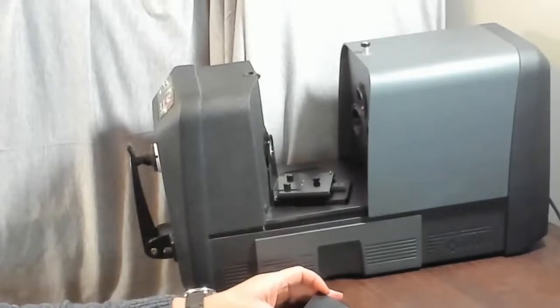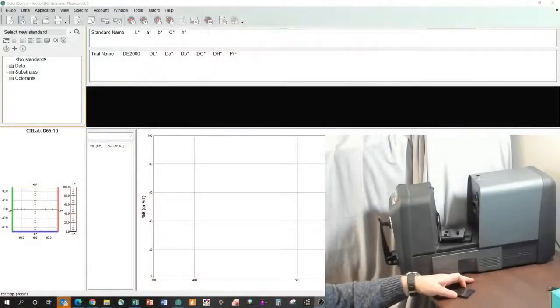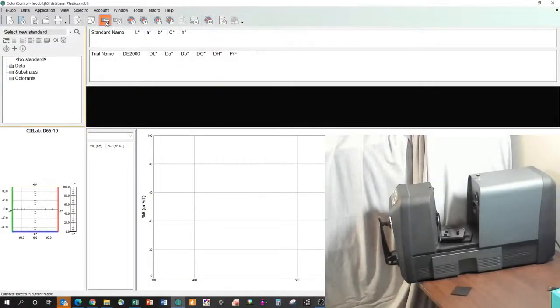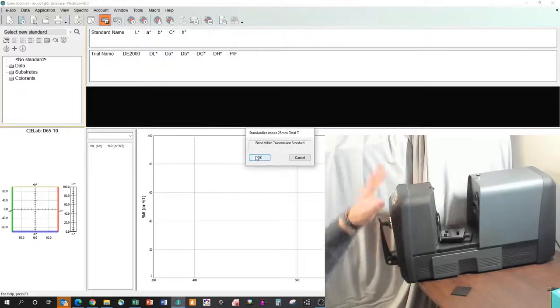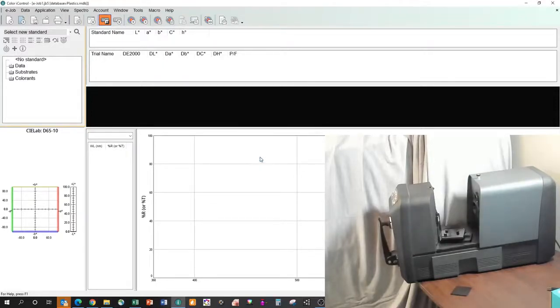So let's switch the view here a moment to see our software and our instrument simultaneously. And we're going to go in to calibrate our transmission measurement. And so the software comes up and tells me to read the white transmission standard. That's just this. Now, typically I'd close the door when I'm doing a measurement if possible. It's not required. We'll leave it open so you can see what's going on. You see the instrument flash as we do the white measurement.